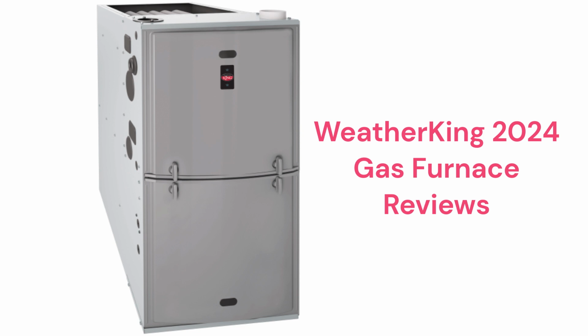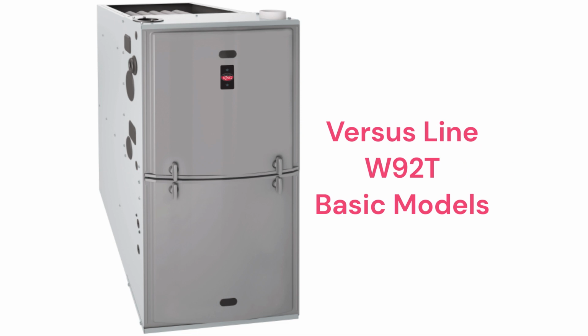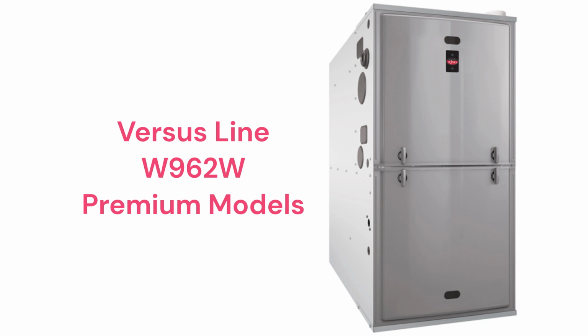The W92T models are basic single-stage furnaces with a 92% AFUE efficiency and a fixed-speed blower motor, while the W962W models are premium two-stage units with a 96% AFUE combustion efficiency. The furnaces are four-way multi-position units which allow the dealers to have less inventory and therefore lower costs.